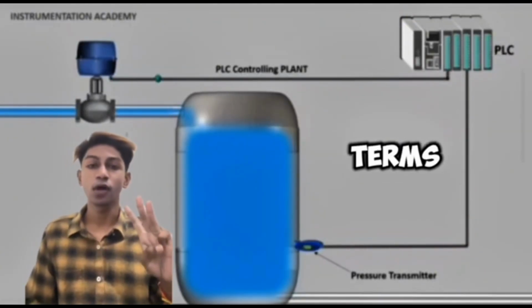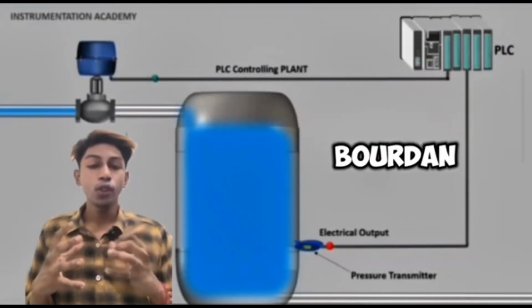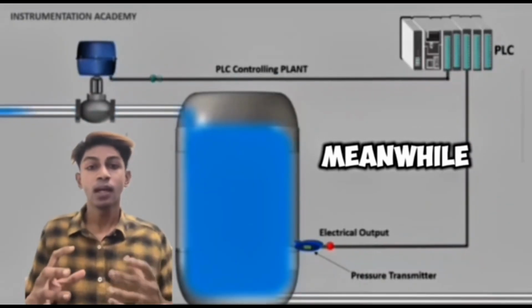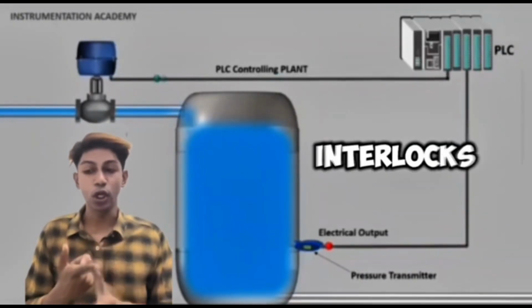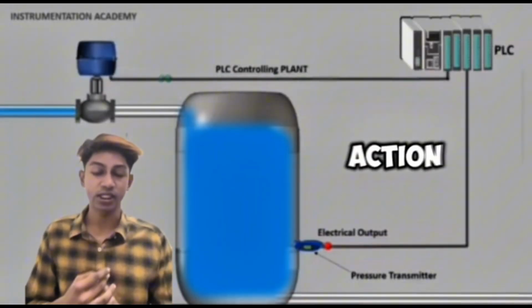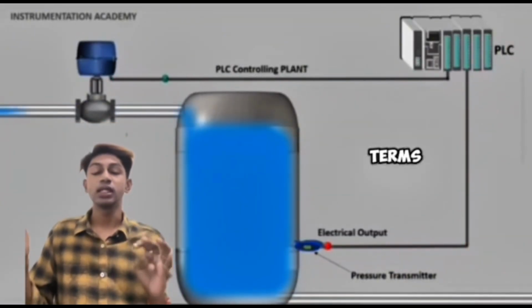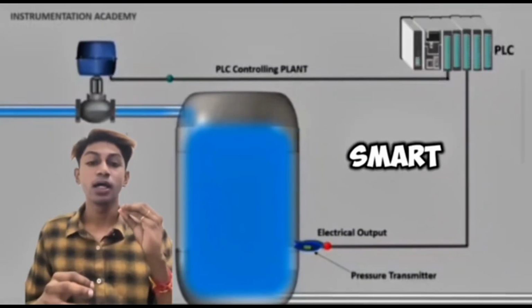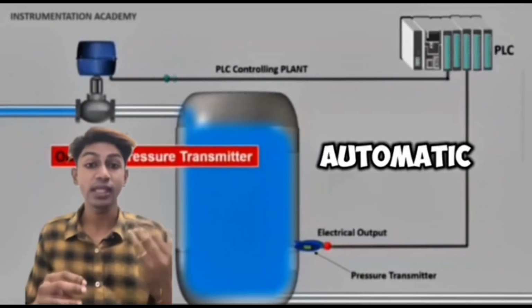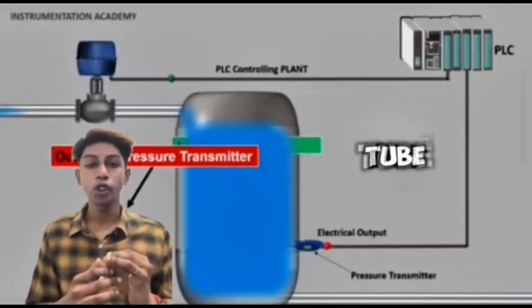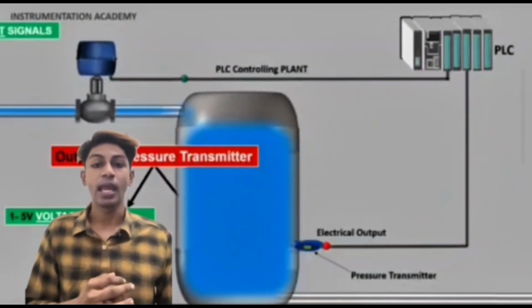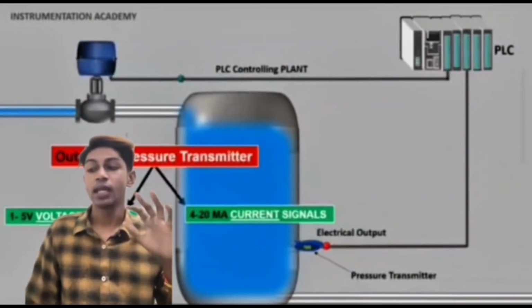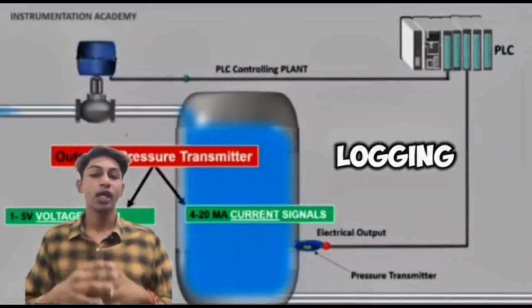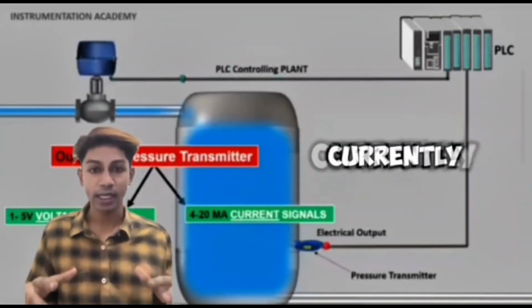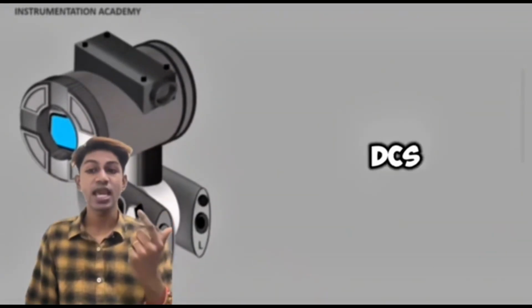Third, in terms of safety. Bourdon tube only provides local safety. Meanwhile, smart DP transmitter has interlocks, alarms, and automatic safety action. Fourth is in terms of data logging. Smart DP transmitter has automatic data logging. Meanwhile, Bourdon tube doesn't have automatic data logging. Fifth, remote logging. Remote logging in Bourdon tube is not available, but smart DP transmitter has SCADA, DCS, and HART communication systems.